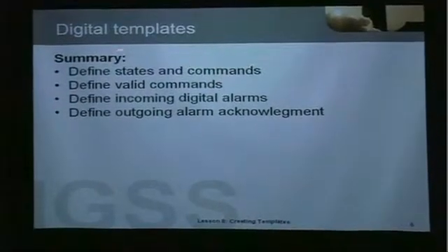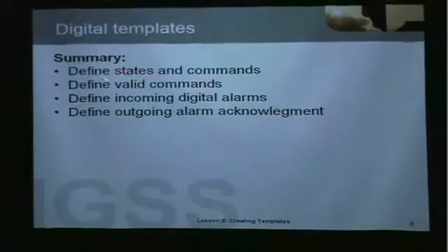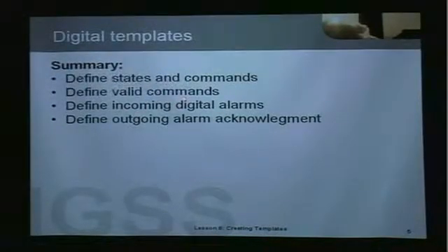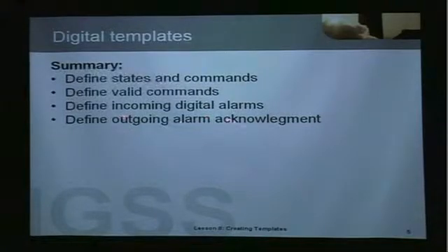When we look specifically at digital templates, we have a number of possibilities. First of all we can define states and commands and give them names instead of the initial 0, 1, 2 that we get. We can also, for each state in a digital object, define its valid commands — what the operator should be able to do when the object is in that particular state. We can define incoming digital alarms and outgoing alarm acknowledgement.